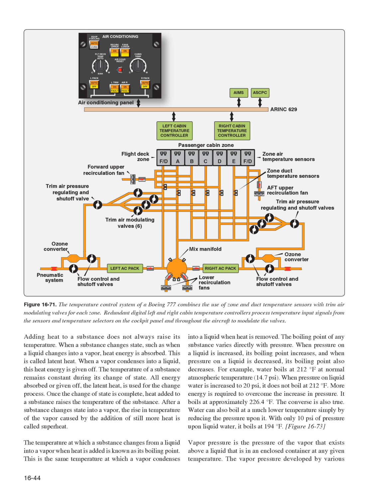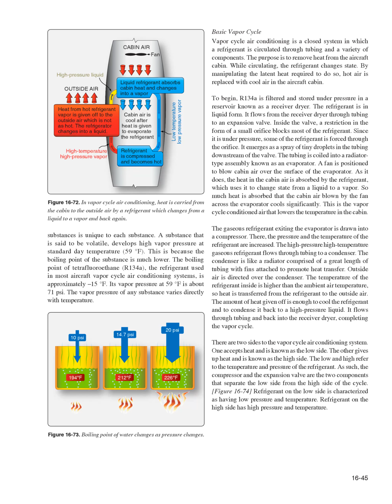Figure 1673. Vapor pressure is the pressure of the vapor that exists above a liquid that is in an enclosed container at any given temperature. The vapor pressure developed by various substances changing from liquid to a vapor and back again is unique to each substance. A substance that is said to be volatile develops high vapor pressure at standard day temperature, 59 degrees Fahrenheit. This is because the boiling point of the substance is much lower. The boiling point of tetrafluoroethane, R134A, the refrigerant used in most aircraft vapor cycle air conditioning systems, is approximately -15 degrees Fahrenheit. Its vapor pressure at 59 degrees Fahrenheit is about 71 pounds per square inch. The vapor pressure of any substance varies directly with temperature.